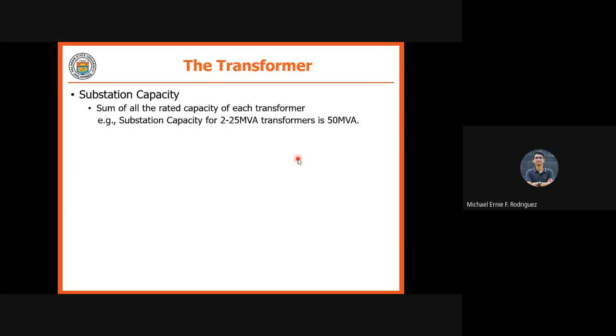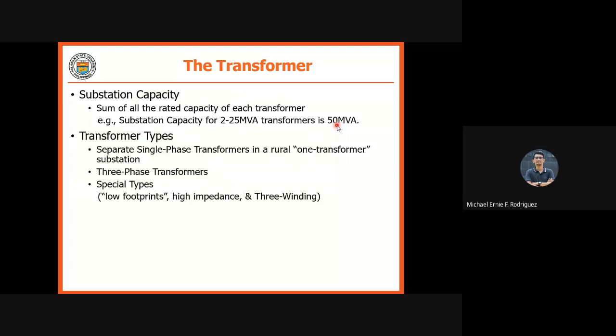So, substation capacity. That is the sum of all the rated capacity of each transformer. Let's say, for example, our Paleco substation, that is 2 by 25 MVA. So the substation capacity for a 2 by 25 MVA transformer is 50 MVA. It's just the sum of the rated capacity. So, 2 times 25, that is 50 MVA. We have different transformer types.